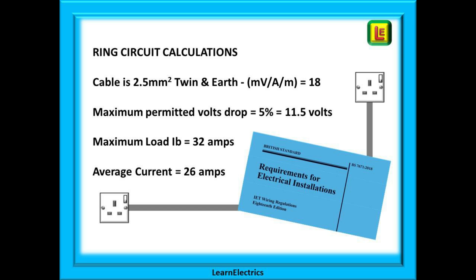The regulations also tell us that the maximum permitted volts drop for this type of circuit is five percent of 230 volts, which is 11.5 volts. Any volts drop above 11.5 volts may start to affect the efficiency and performance of appliances that are connected to it, and the cables may also begin to overheat. Our maximum load is 32 amps and our average load is 26 amps.